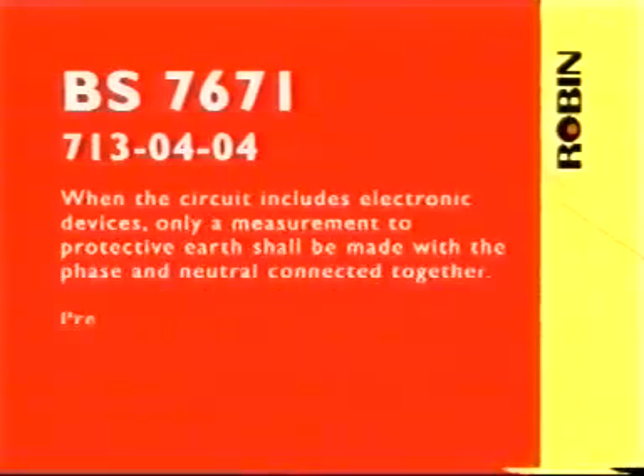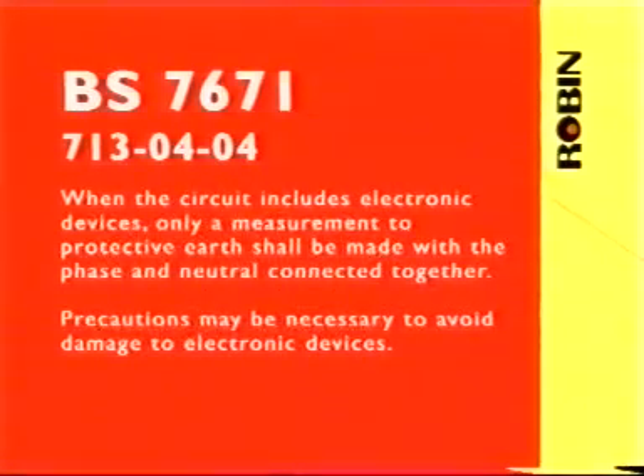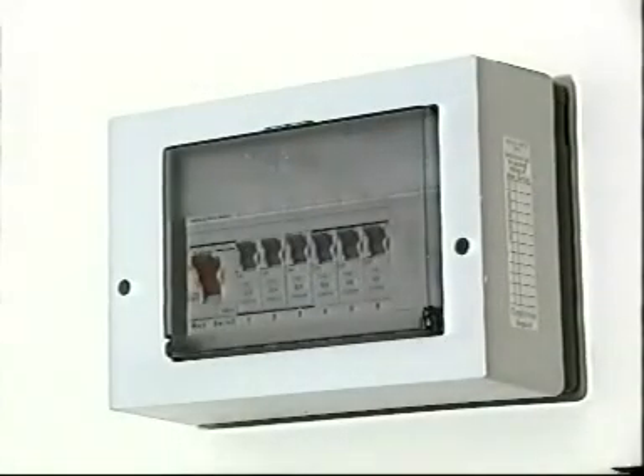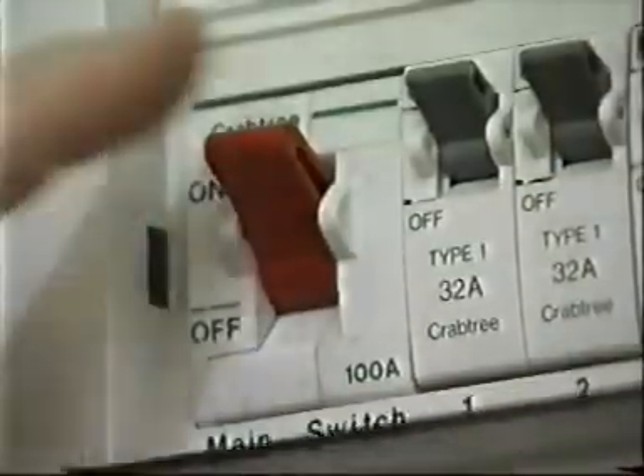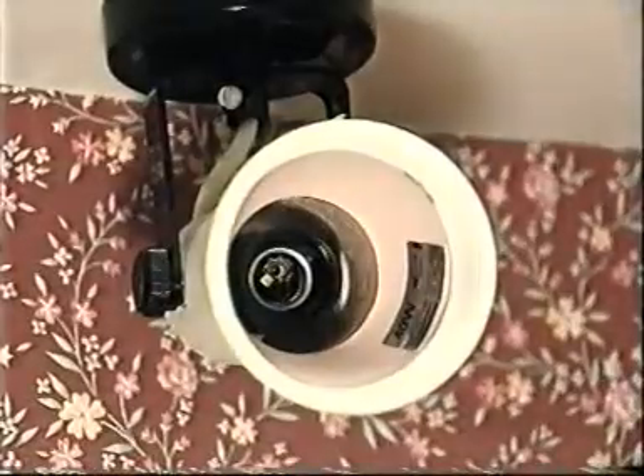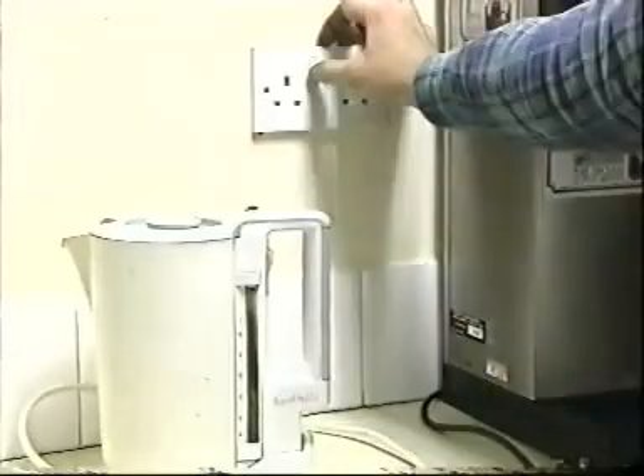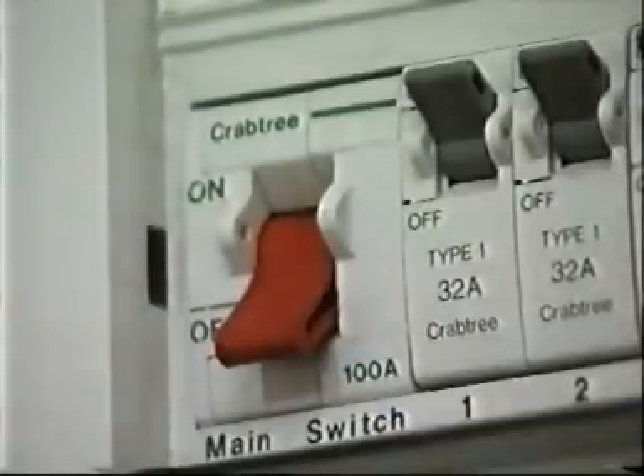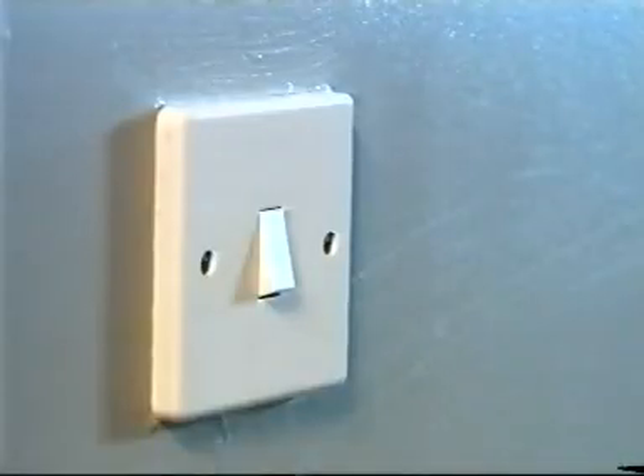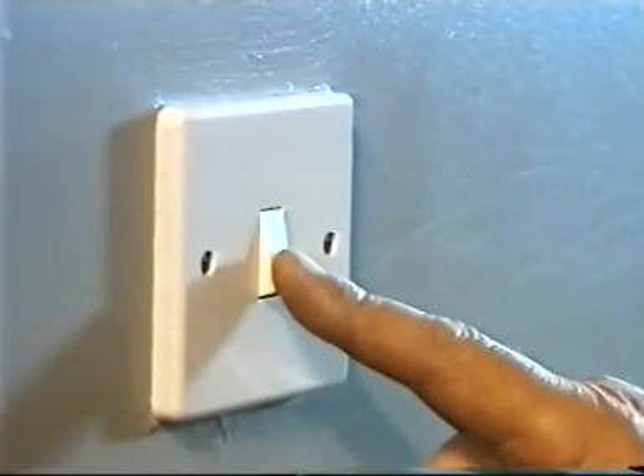Where electronic filters are present between exposed conductive parts of equipment and live parts, a test between live conductors and earthed exposed conductive parts only is made, not a test between live conductors. The test to earth must be carried out on the complete installation with the main switch off, lamps removed and equipment disconnected. Fuses must be in, circuit breakers closed and all final circuit switches closed.